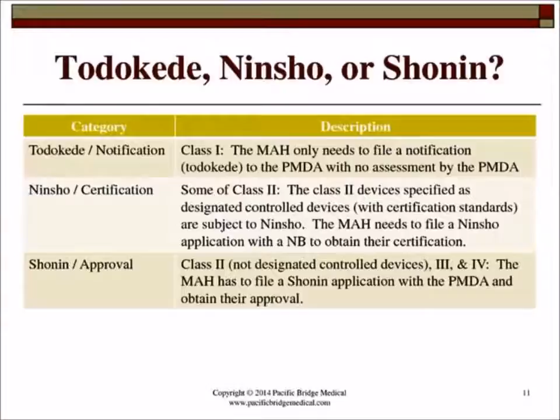But according to the new revisions of the PMDA, by the end of 2014, more certifications will be accepted for Class 2 and some Class 3 products. So that means that most Class 2 products, or almost all the Class 2 products, and some of the Class 3 products will receive certification from a third party and not need to go through the PMDA. So the next few pages give a further breakdown on which class the product is in, and if the product meets certain standards or clinical data is required, et cetera.